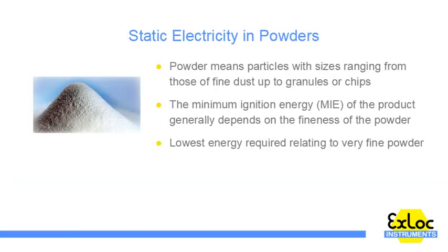Static electricity in powders. In this section, the term powder means particles with sizes ranging from those of fine dust up to granules or chips. The ease with which a given powder can be ignited by discharges or sparks due to static electricity is characterized by the minimum ignition energy, or MIE, of the product, and this generally depends on the fineness of the powder, the lowest energy required relating to very fine powder.